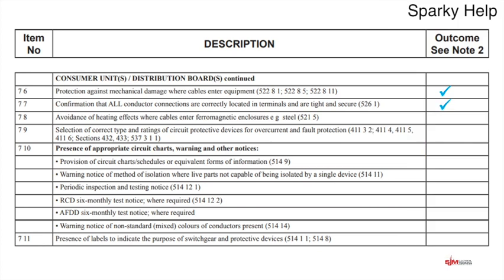Avoidance of heating effects where cables enter a ferromagnetic enclosure, i.e. a steel enclosure. So what is that? That's single core cables passing through a gland plate. So this would have been incorrect. However, what they have done here is they have put a slot in between the holes, and that will overcome this problem of eddy currents in the gland plate. As long as we did that, that's fine.